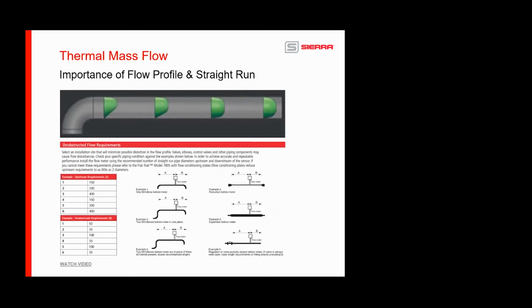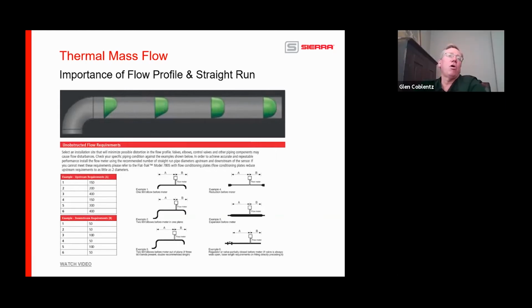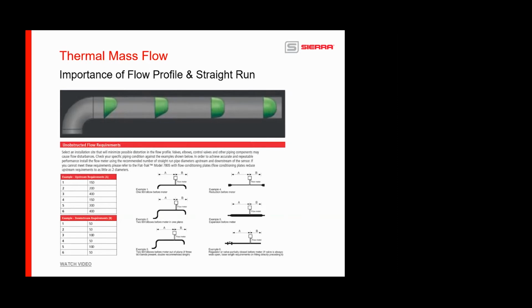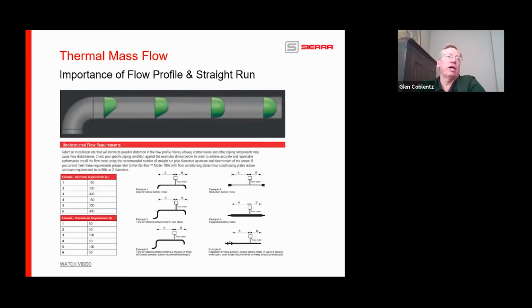Second question is regarding custody transfer on any of our devices. Are they rated for that, specifically the 780S? None of our meters are rated. Are we talking custody transfer of natural gas? The question does not specify, but I would assume natural gas. Okay. So custody transfer of natural gas has to be an AGA approved meter. None of our meters are AGA approved. AGA approves a technology, not a manufacturer. So it would be up to Sierra to cover that entire bill of that, and we're just not in a position to do that at this point in time. But it's something they're always looking at because we've got the best meter out there in terms of accuracy, and it far exceeds what the AGA requires. It's just you've got to pay all the money to get the AGA stamp. We're not there yet.